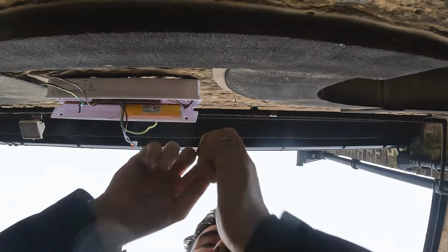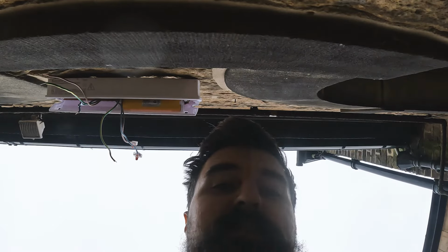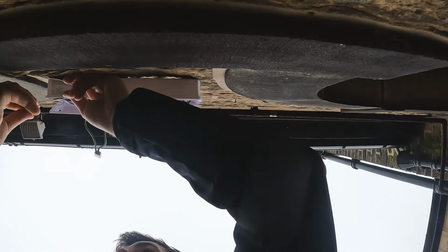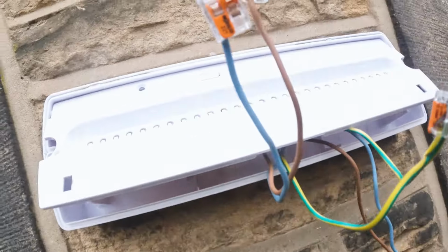The cable's down, so they'll go off to some circuits which we need to look into and find. But these ones going up will come live, won't they? So what I'll do is I'll cap them all off. We can bank earths together, because that doesn't really matter, because earth is common. We'll separate those lines then. Line and neutral. Right, let's get another way going. So, they're the good ones, they're the bad ones.